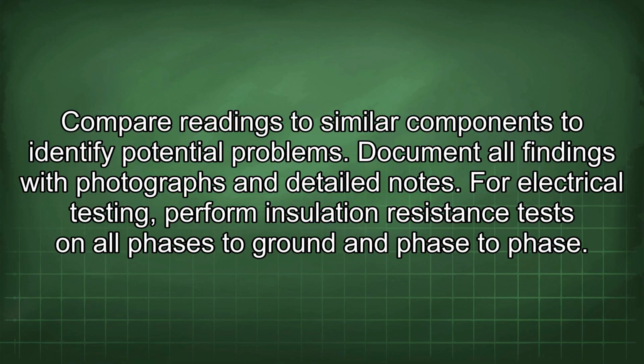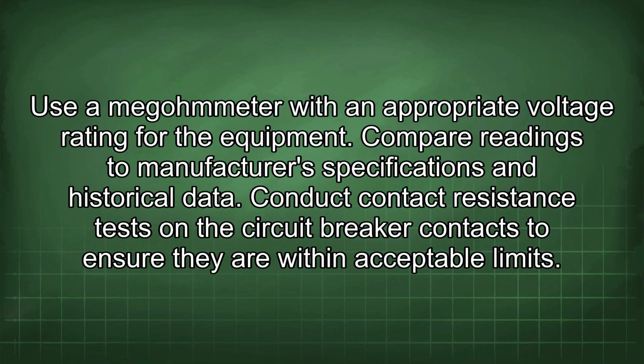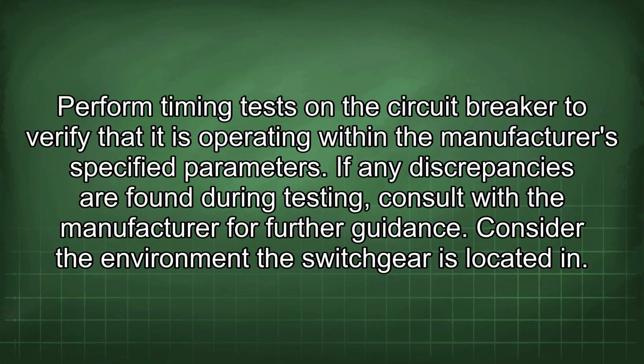For electrical testing, perform insulation resistance tests on all phases to ground and phase to phase. Use a megohmmeter with an appropriate voltage rating for the equipment. Compare readings to manufacturer's specifications and historical data. Conduct contact resistance tests on the circuit breaker contacts to ensure they are within acceptable limits. Perform timing tests on the circuit breaker to verify that it is operating within the manufacturer's specified parameters. If any discrepancies are found during testing, consult with the manufacturer for further guidance.